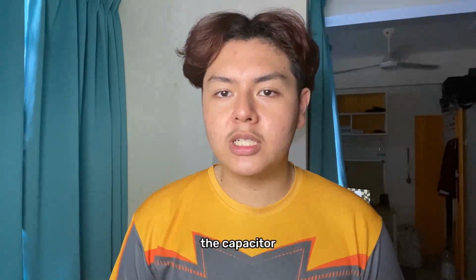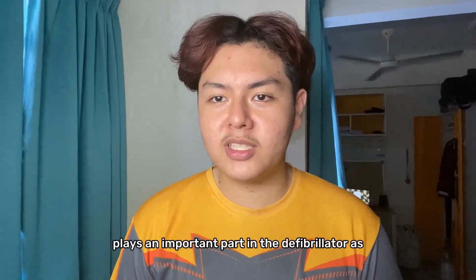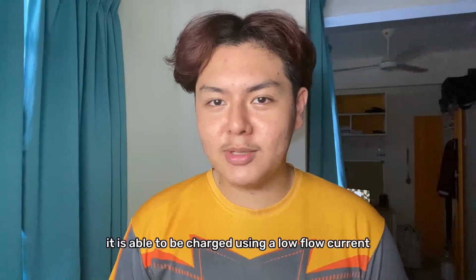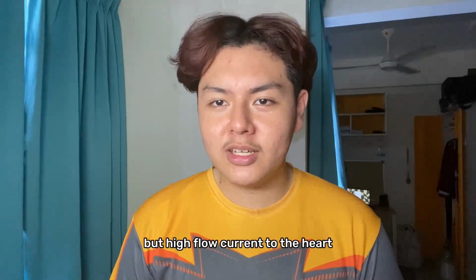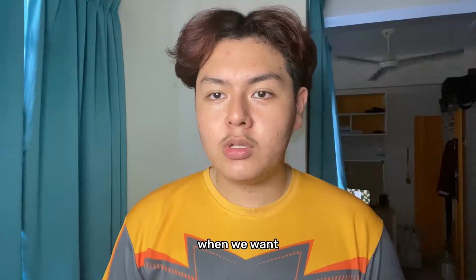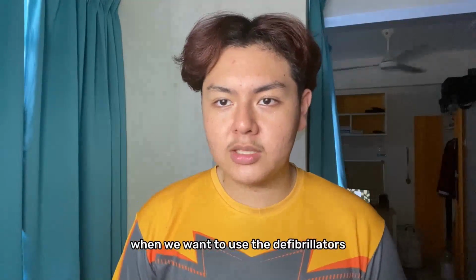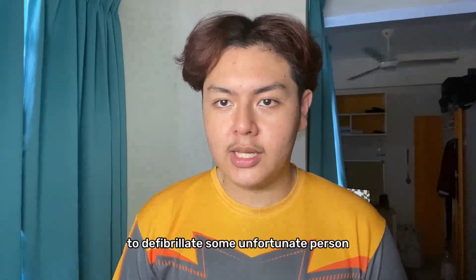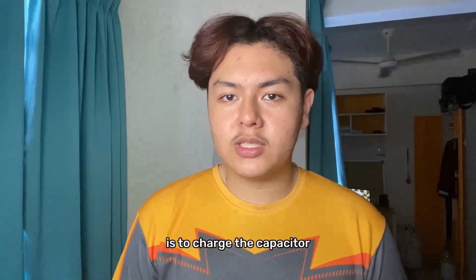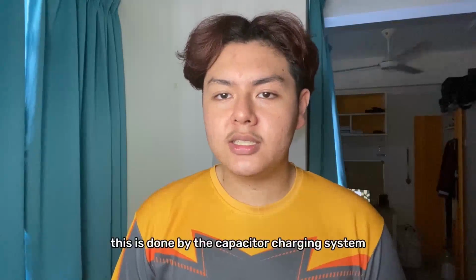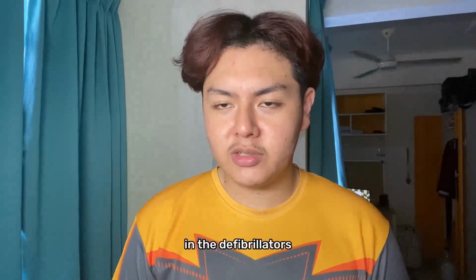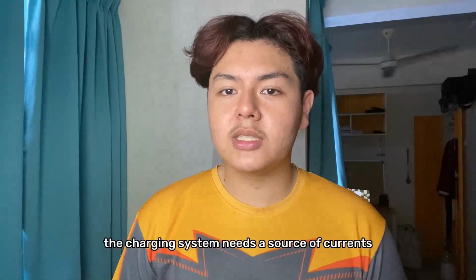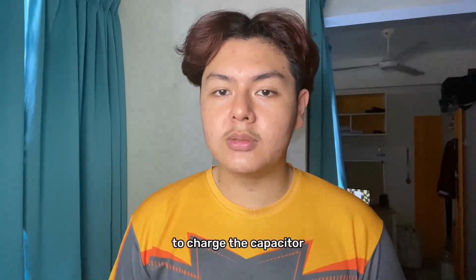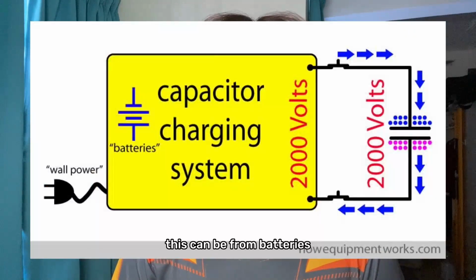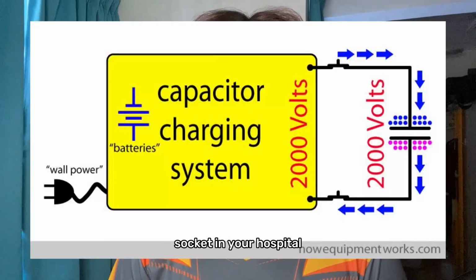As mentioned before, the capacitor plays an important part in defibrillators and it is able to be charged using a low flow current, and then is able to discharge a brief but high flow current to the heart. When we want to use the defibrillator to defibrillate some unfortunate person, the first thing we need to do is to charge the capacitor. This is done by the capacitor charging system in the defibrillator. The charging system needs a source of current to charge the capacitor. This can be from batteries or from the wall power socket in your hospital.